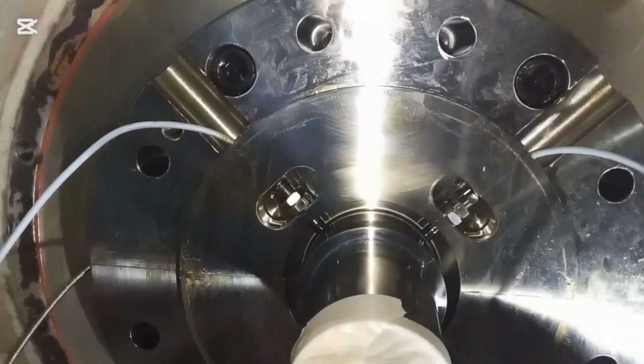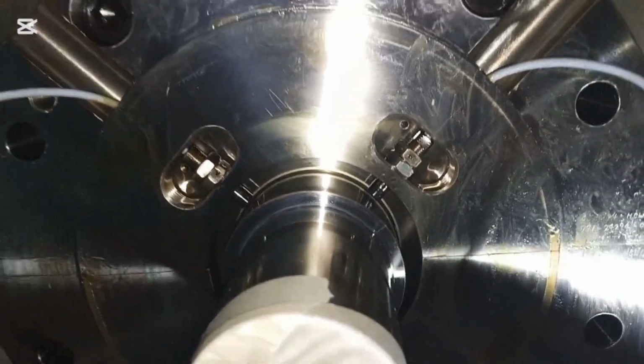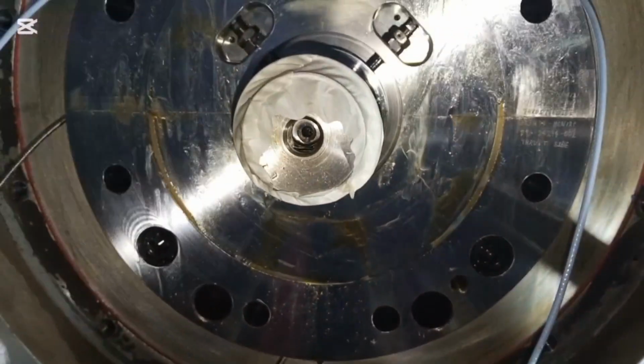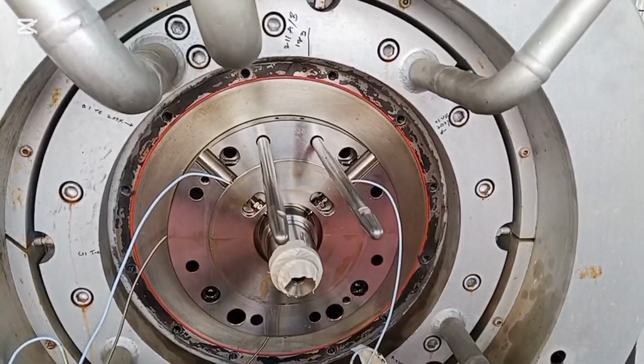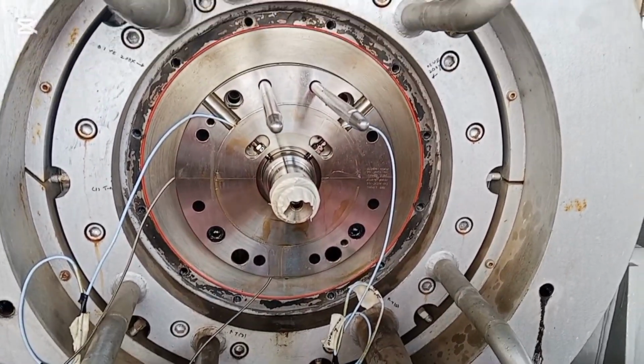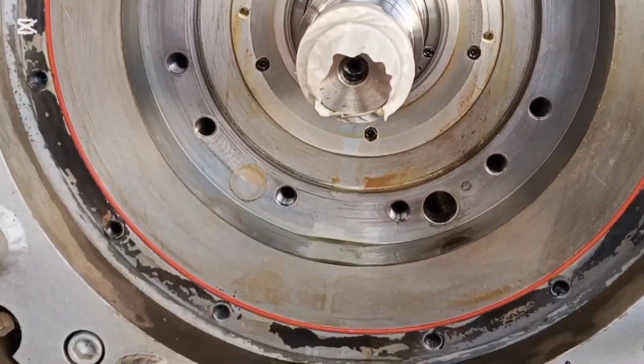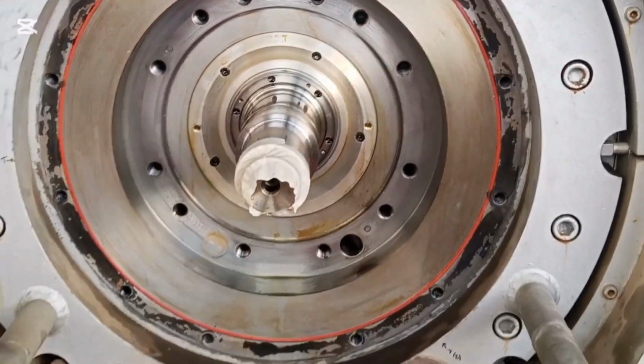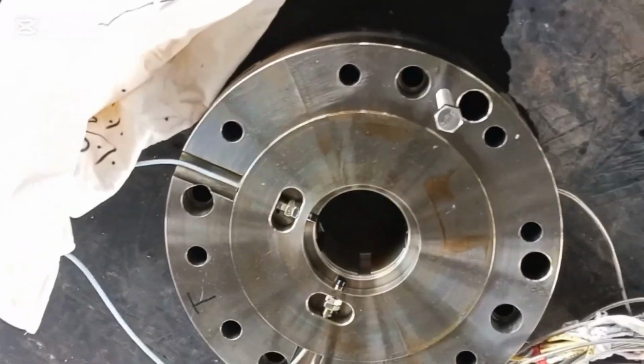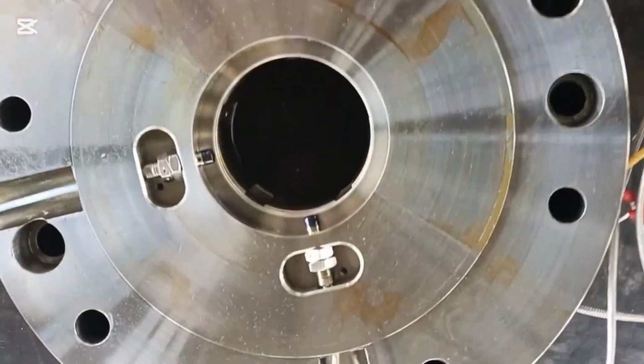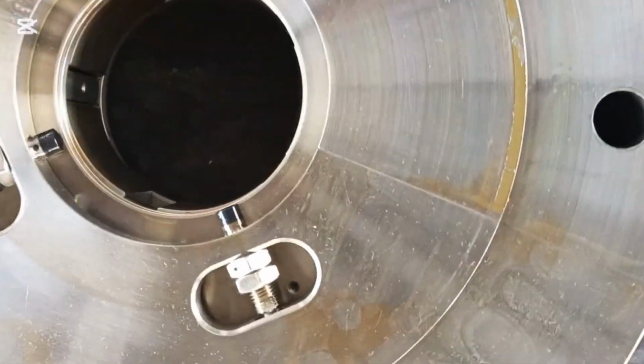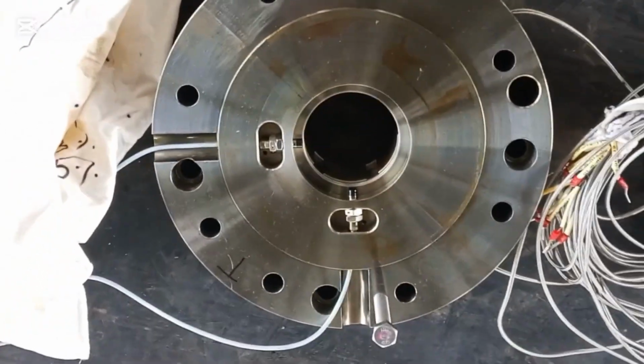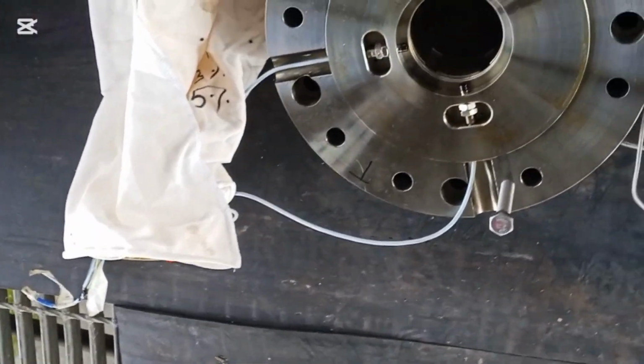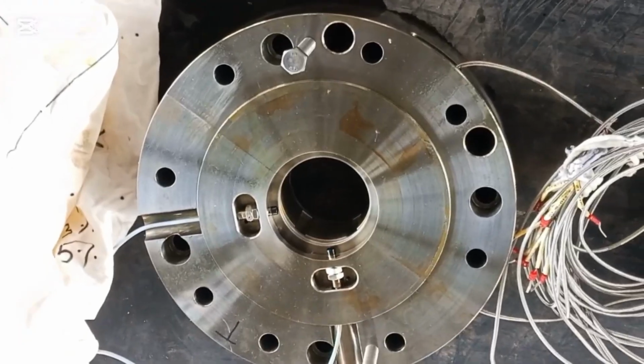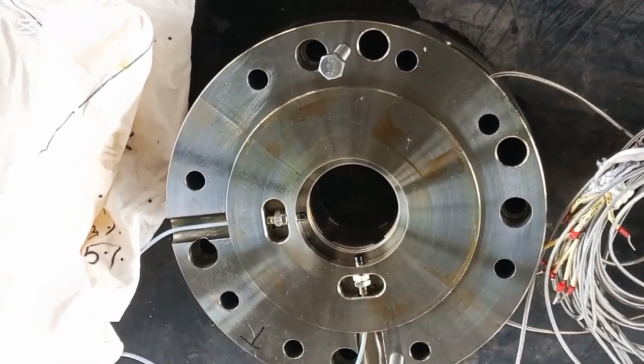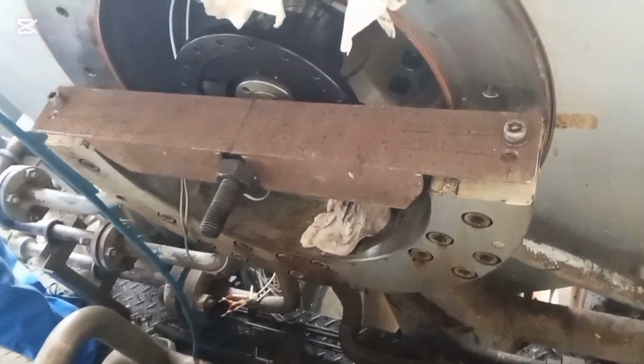You see, here is some sensor. This is the bearing sensor, vibration sensor, and this sensor is very complicated to connect and also dismantle and to adjust its position. So as the sensor was okay, we did not dismantle the sensor from its base, and it stays connected with the unit, and at the time of assembling we connected this item with the sensor.